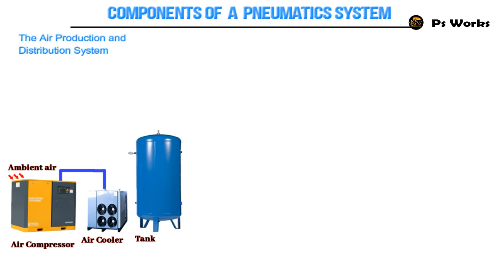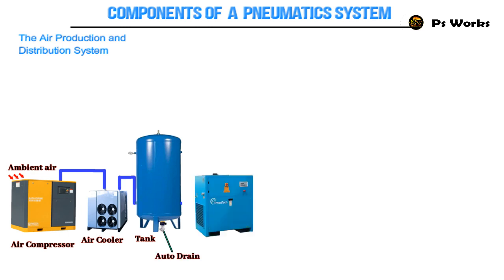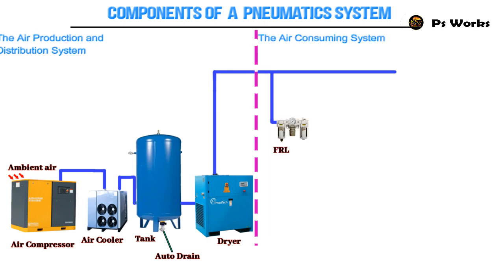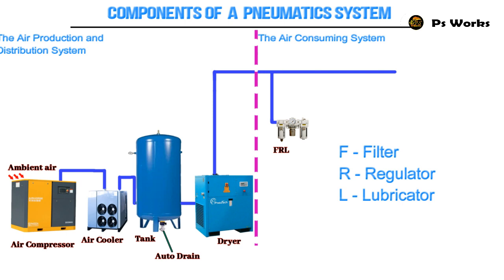Tank: the compressed air coming from the compressor is stored in the air receiver. Auto drain: drains all the water condensing in the tank without supervision. Dryer: the water vapor or moisture in the air is separated from the air by using a dryer. FRL: an FRL unit comprises a filter (F), regulator (R), and lubricator (L). These individual units can combine into one unit to ensure clean air in a pneumatic system, or each component can be used individually. A proper FRL unit provides higher reliability of downstream components, reduced power wastage from overpressurization, and increased component lifetime.